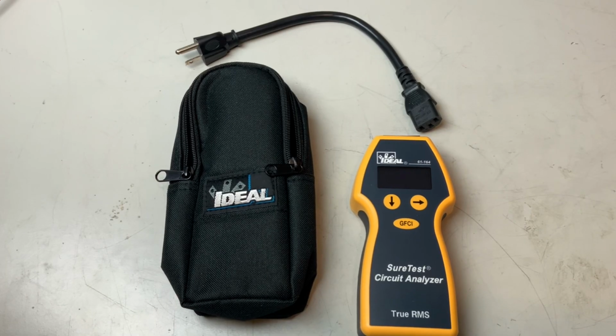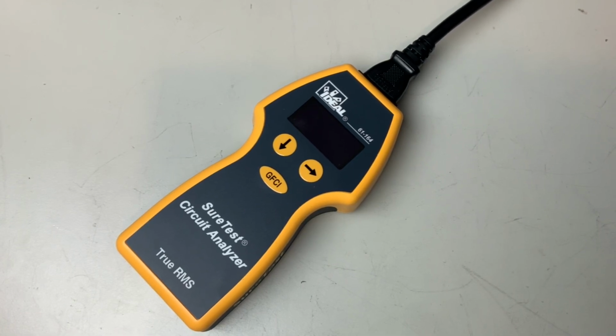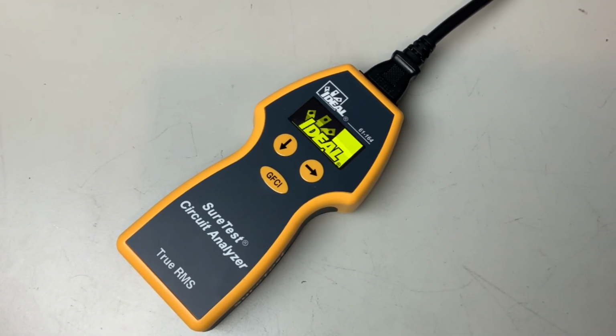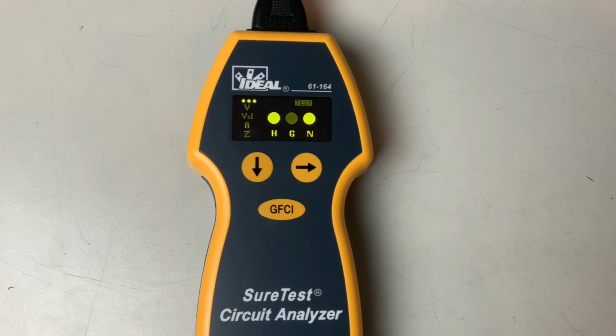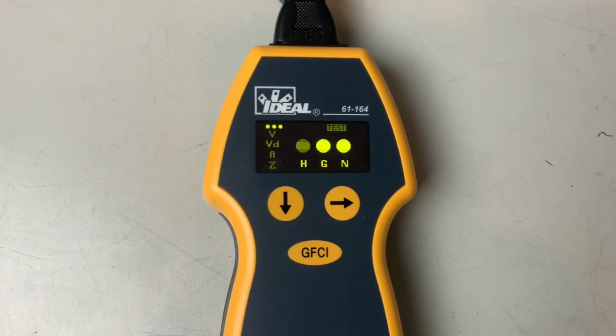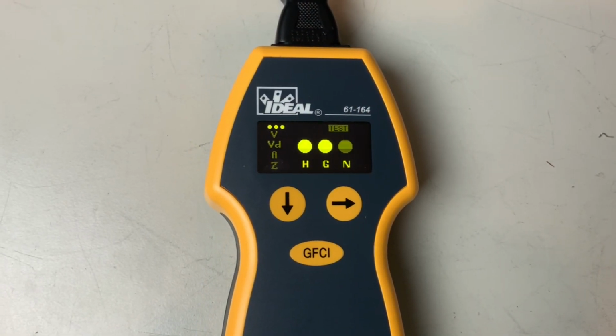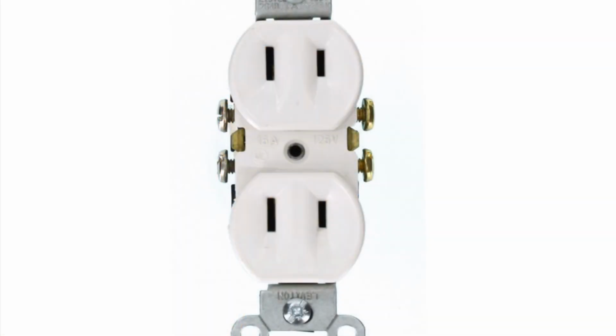The unit comes with a small pigtail cord that is replaceable, so you can always put a longer one on if you want, and a carrying case. There are no batteries because it is powered from the outlet that it is measuring. When you first plug the unit in, it takes about 5 seconds for the screen to come up, and if everything is wired properly, it will show you 3 dots indicating proper wiring. It will also show you common wiring errors like an open ground or a hot neutral reverse, but it will not show an open neutral because it needs the neutral to power up the unit.